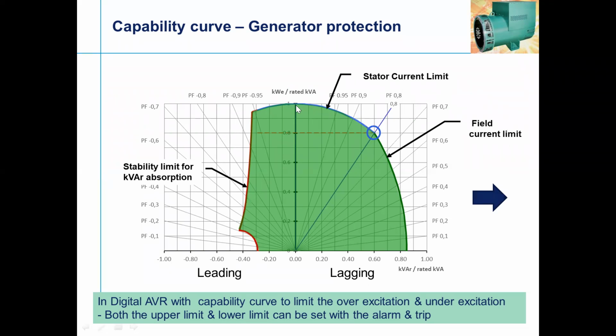Why not leading? Yes, if the generator has the capacity. Whether Srinivasan can run 50 kilometers per hour means he should have the body scope or the design, the physical strength to do that. Like that, the generator capacity kVA should also be selected so that the machine can do it. This is why the designer plays an important role in the machine selection.